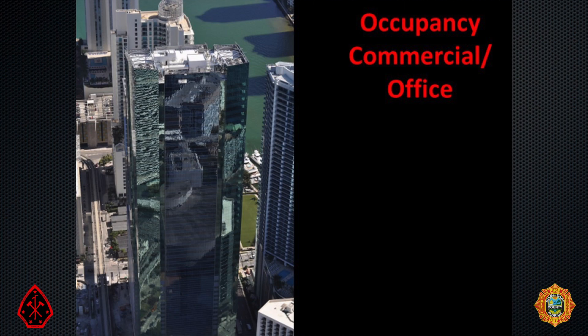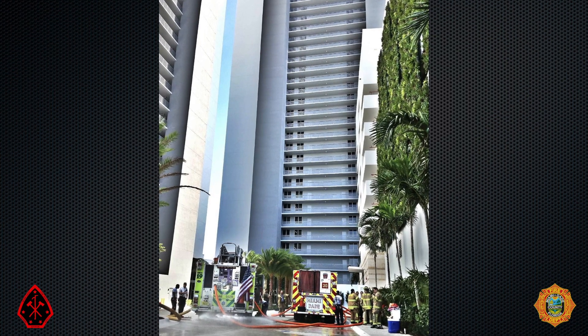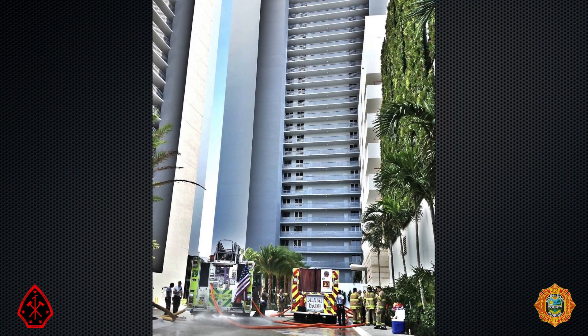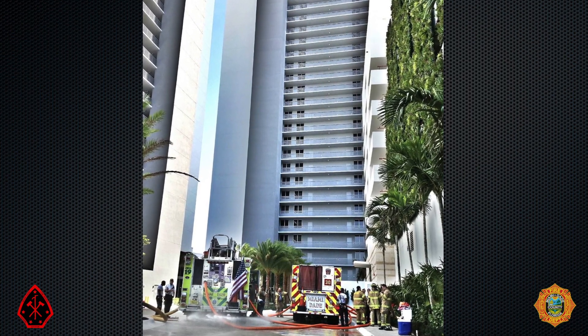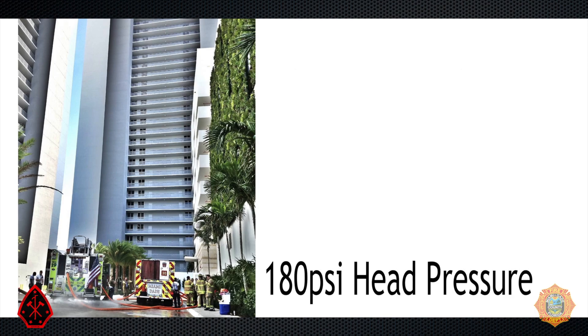Additionally, the height of floors in office buildings as well as new residential buildings are generally 12 feet or higher. As a result, we calculate the head pressure or elevation loss as 6 psi per floor. Now consider a modern 30-story residential or office building. The calculation would be 30 floors times 6 psi per floor, which equals a head pressure of 180 psi at the base of its standpipe risers.